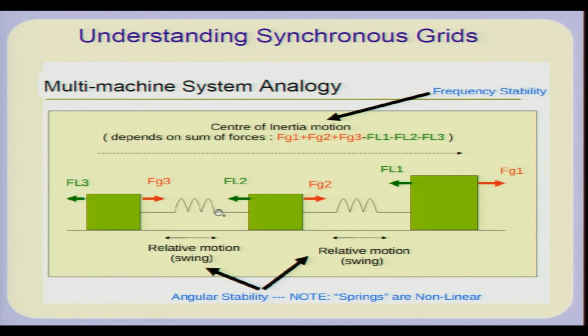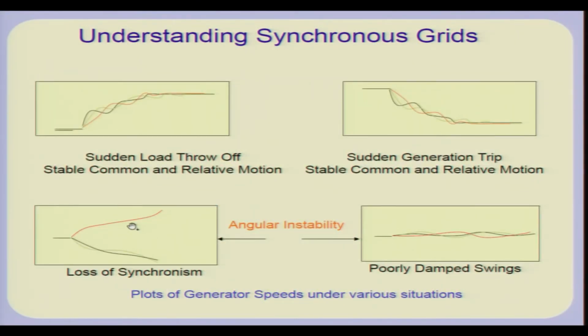Now, if it is a linear spring, the restorative force becomes proportional to the stretch of the spring, but in case it is a nonlinear spring, like in a power system where the electrical power is proportional to sine of delta 1 minus delta 2, as the stretch increases, a point comes after which the spring loses its restorative force, that is, sine of delta 1 minus delta 2 becomes negative, and the mass is no longer able to come back. So, in such a situation you do not have oscillatory motion, but because of a large disturbance some generator may actually lose synchronism. In fact, it is an unstable situation.